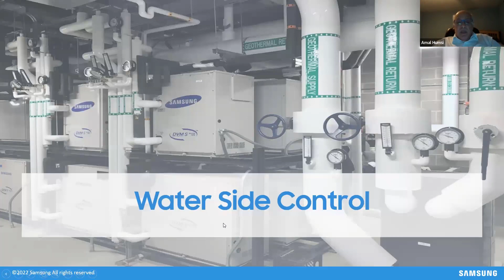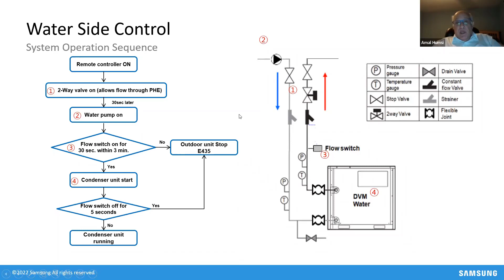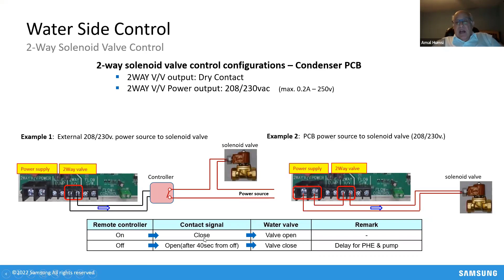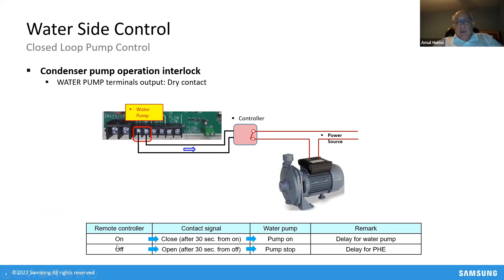In terms of the water side controls, again, we make it simple. Basically, if you want to control the water flow to the unit, you can have a two-way solenoid control valve. That's not required, but if you want to, you can, and there are terminals on the board that will control that. You can actually wire it from our board too, so when the remote controller is on, you close the contacts and the valve will open. The other thing you can do is interlock the pump with the system, so when the remote controller is on, the pump is activated.